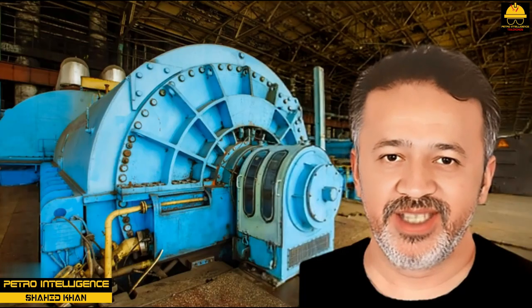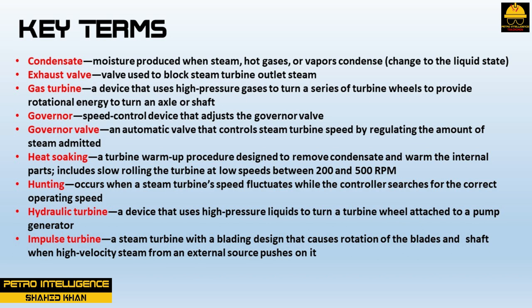Before starting the course, let us have a look at key terms. Condensate is moisture produced when steam, hot gases, or vapors condense — that is, changed to the liquid state. Exhaust valve is a valve used to block steam turbine outlet steam. Gas turbine is a device that uses high pressure gases to turn a series of turbine wheels to provide rotational energy to turn an axle or shaft. Governor is a speed control device that adjusts the governor valve. Governor valve is an automatic valve that controls steam turbine speed by regulating the amount of steam admitted. Heat soaking is a turbine warm-up procedure designed to remove condensate and warm the internal parts, including slow rolling the turbine at low speeds between 200 and 500 RPM.